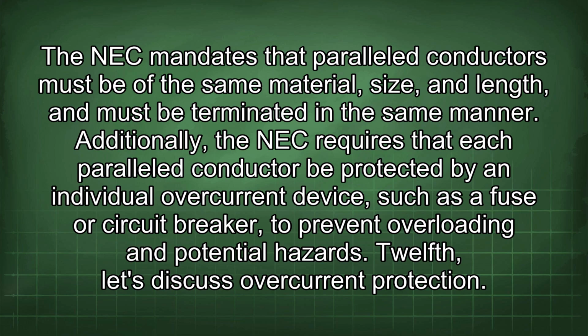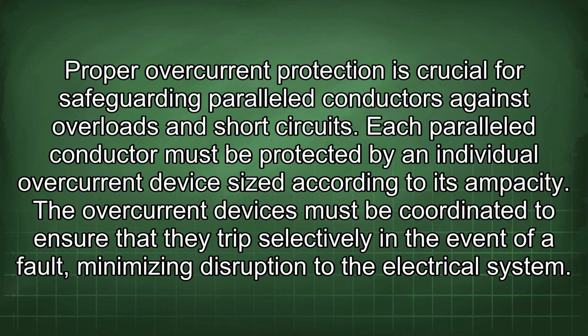Additionally, the NEC requires that each parallel conductor be protected by an individual overcurrent device, such as a fuse or circuit breaker, to prevent overloading and potential hazards. 12th, let's discuss overcurrent protection. Proper overcurrent protection is crucial for safeguarding parallel conductors against overloads and short circuits.